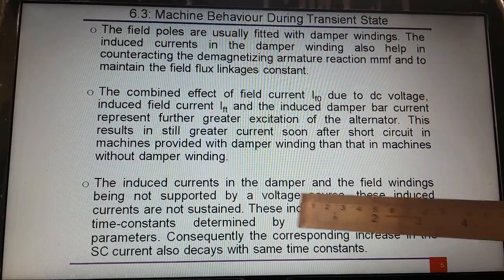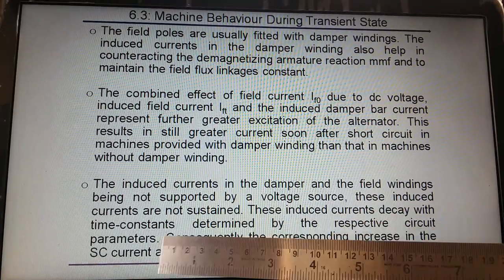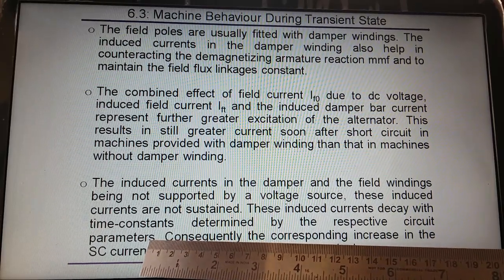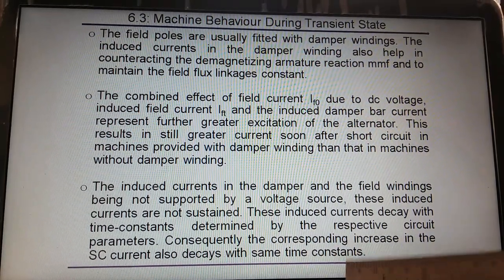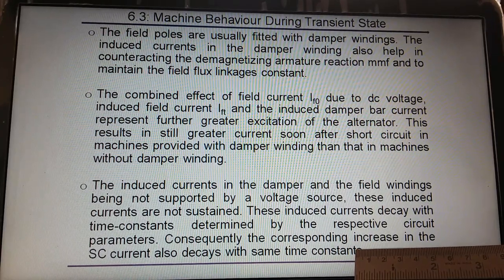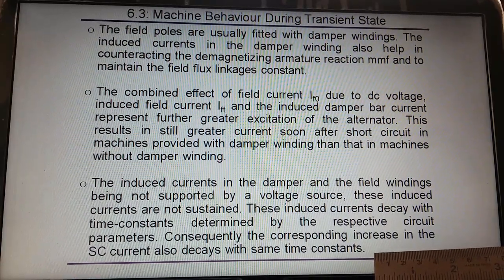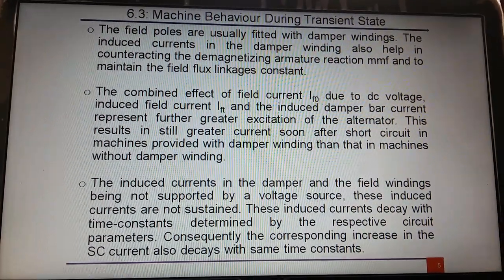Because these induced currents in the damper and field winding are not supported by a DC source, these currents will not be sustained for a long time. They will decay with a time constant — the time constant tau is equal to L by R, where L is inductance and R is resistance. Consequently, the corresponding increase in short circuit current also decays with the time constant. One by one the induced currents will die out, and the short circuit current will also die out, depending upon the time constants of the damper winding and field winding.